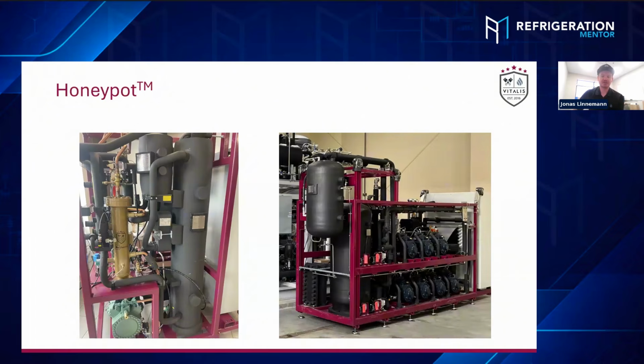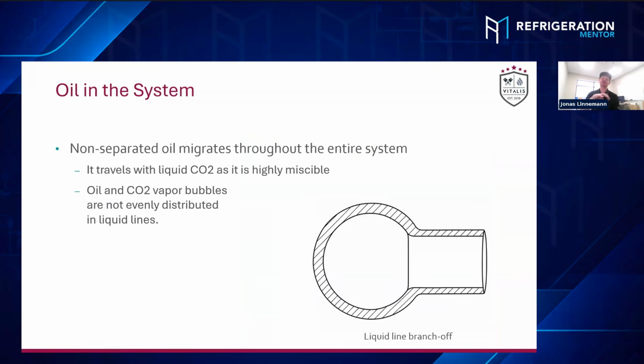Okay. So one more topic. We talked the whole time about basically the primary oil circuit, but I want to talk a bit about what's actually happening with the oil as soon as it travels out into the system. So if you carry oil out into the system, it typically passes through the gas cooler, through the high pressure valve, down into the liquid receiver. You've mentioned a few times before something about winter cases. In the winter, it's sometimes difficult because there are very low temperatures inside the gas cooler, so you will catch some oil there as well. But typically, it's ending up in the liquid receiver and then traveling through the liquid line into the field piping.